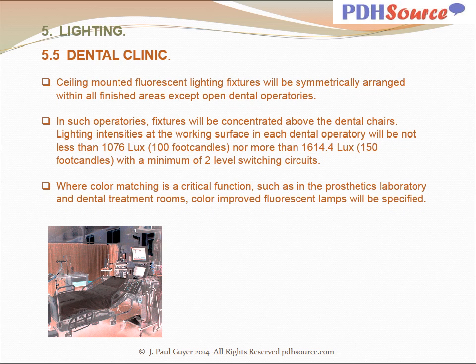In dental clinics, ceiling-mounted fluorescent lighting fixtures will be symmetrically arranged within all finished areas except open dental operatories. In such operatories, fixtures will be concentrated above the dental chairs. Lighting intensities at the working surface in each dental operatory will be not less than 100 foot candles nor more than 150 foot candles with a minimum of 2-level switching circuits. Where color matching is a critical function, such as in the prosthetics laboratory and dental treatment rooms, color improved fluorescent lights will be specified.